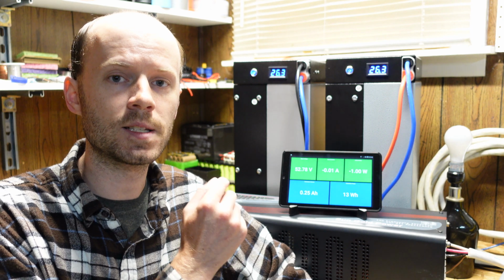You need 25 watts to turn this on, and it has to be 25 watts on one specific leg. That 25 watts can't be applied to the second leg, and it's got to be pretty much a resistive load. So if I put a 60 watt light bulb on this, sure, it's going to turn on. If I plug a space heater, sure, it's going to turn on.